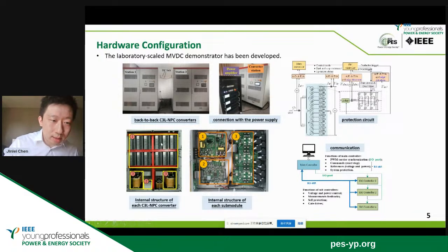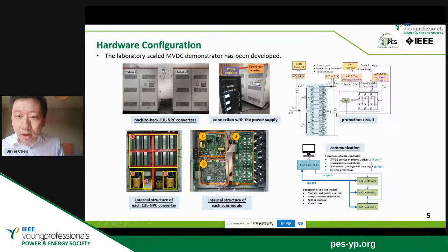In the left corner figure, I put the internal structure of each cascaded three-level NPC converter. All of the submodules are at the top, and at the bottom there are two isolation transformers, and also another main controller. It is used to communicate with the submodules to coordinate all the local controllers. Each local controller is shown here. It includes three parts. The first is the power supplies for the PCB board, and the other is the DSP board, which is a microcontroller, and also there are three-phase gate drivers to drive the IGBT power modules, and also protection circuits and communication circuits. The communication circuit is based on the RS485 cable using the Modbus protocol.